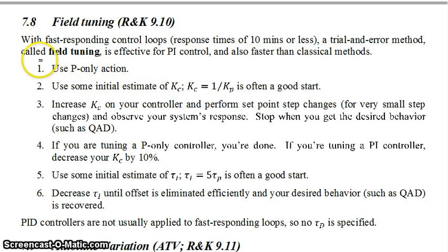The way to do this method, field tuning, is first you use proportional only action. You use some initial estimate of your proportional constant. In this case, 1 over your process gain K_c = 1/K_p is often a good start.